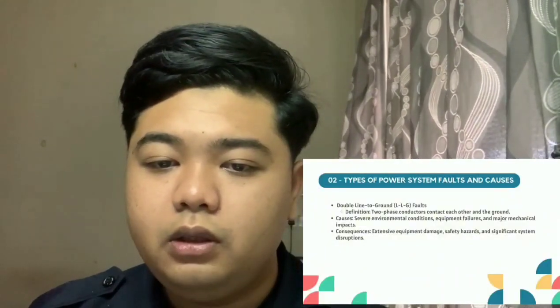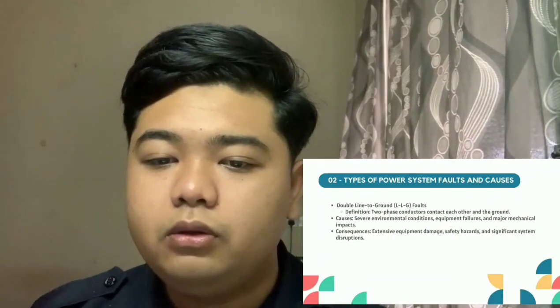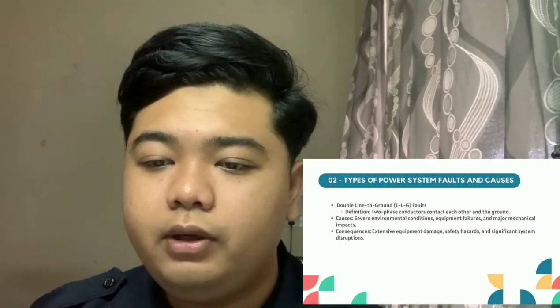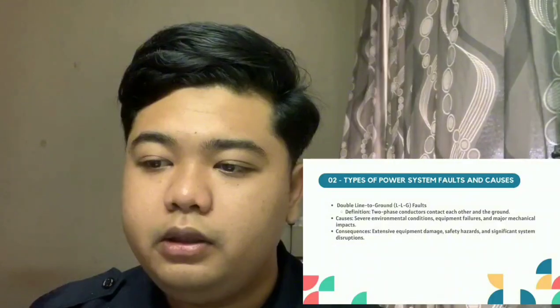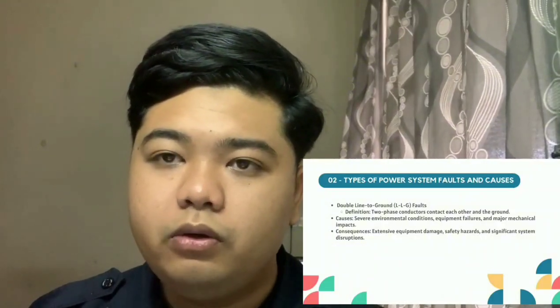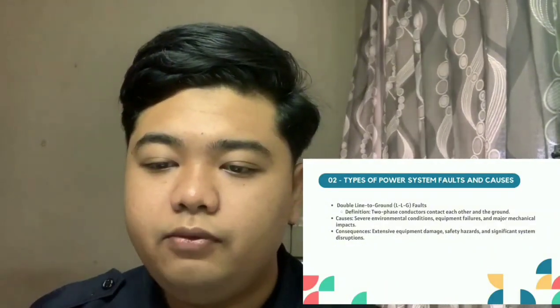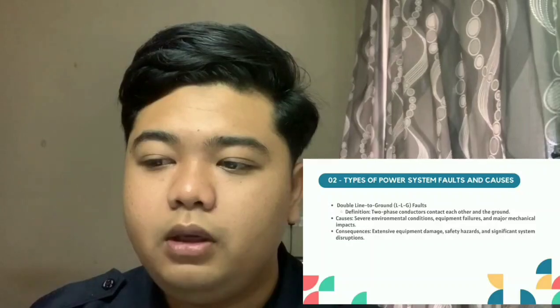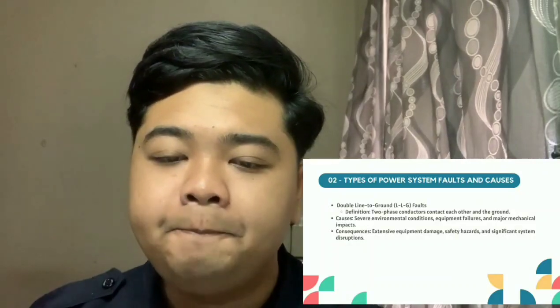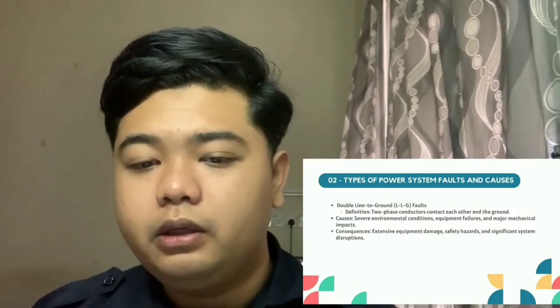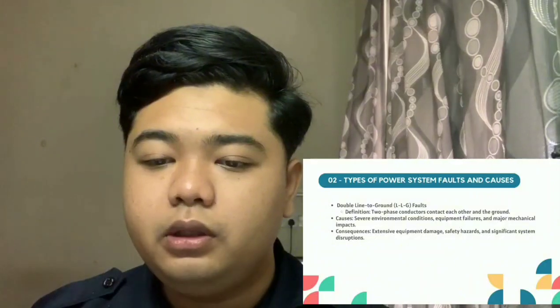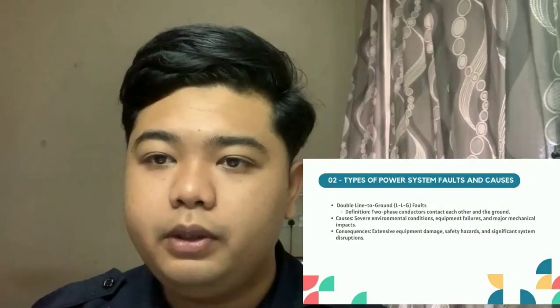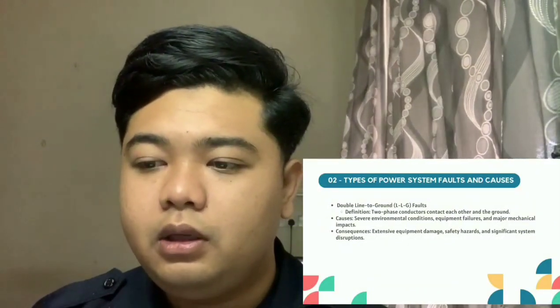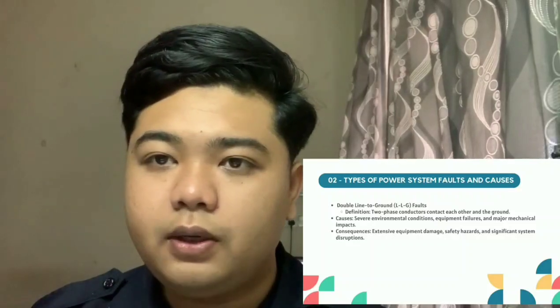Next is the double line to ground fault, which is when two phase conductors contact each other and the ground. The causes of this fault are severe environmental conditions, equipment failure and major mechanical impact. The consequences are extensive equipment damage, safety hazards and significant system disruption.